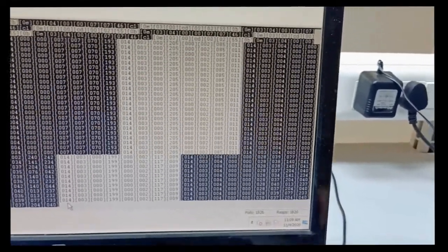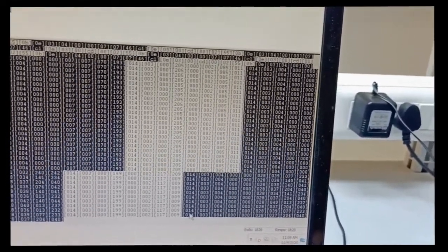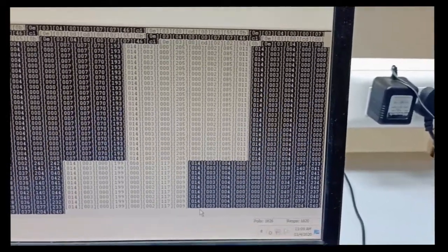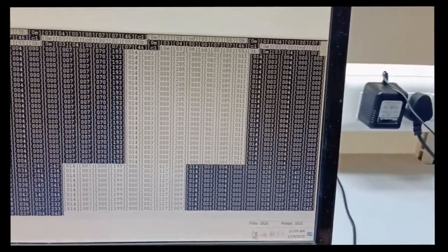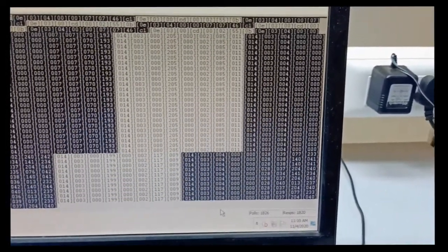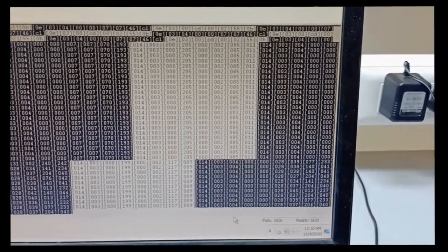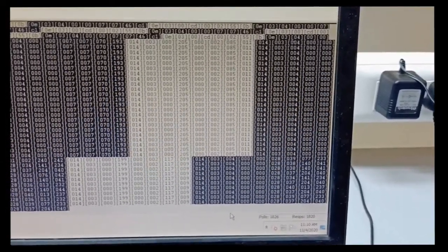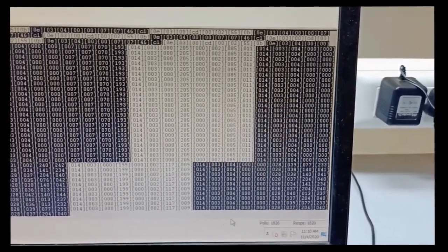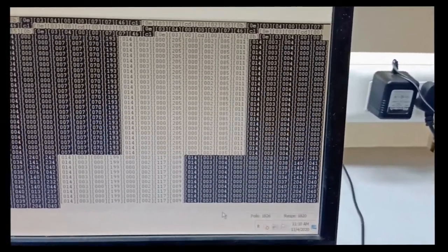In response to this query, the meter is sending this response. The first byte is the meter ID, the second byte 03 is the query type, then the third byte is 4. As per the request we have asked for 2 integers, so in response to that it is sending 4, which is 2 multiplied by 2.